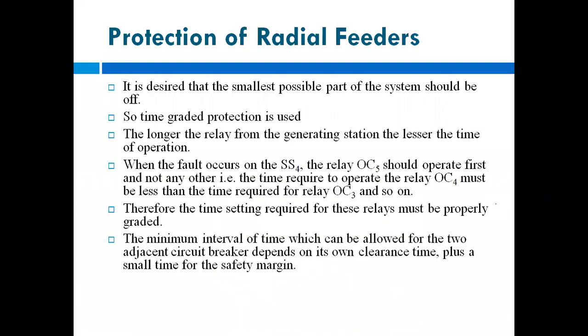The time required for the closer relays is more than for the relays set at a longer distance. Therefore the time settings of these relays must be properly graded. The minimum time interval allowed between two adjacent circuit breakers depends on the breaker's own clearance time plus a small safety margin.